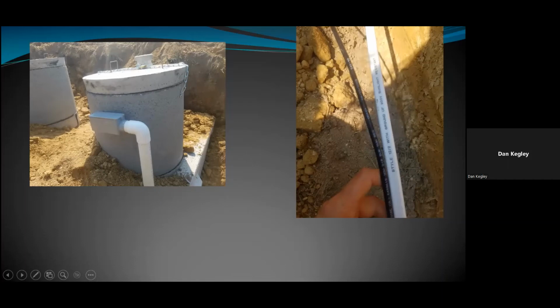There was a question about whether you can have these in the same junction box. The answer is the code says that as long as the low voltage cable outer casing is rated for the highest voltage of the other cable next to it. So in other words, let's assume it's a 120 volt pump, so this cable here is going to have 120 volts in it. They do make a low voltage cable that's 300 volt rated. So if this was a 300 volt outer casing rated cable, then it would be acceptable to be in the same junction box with the other cable, if it was passing through.